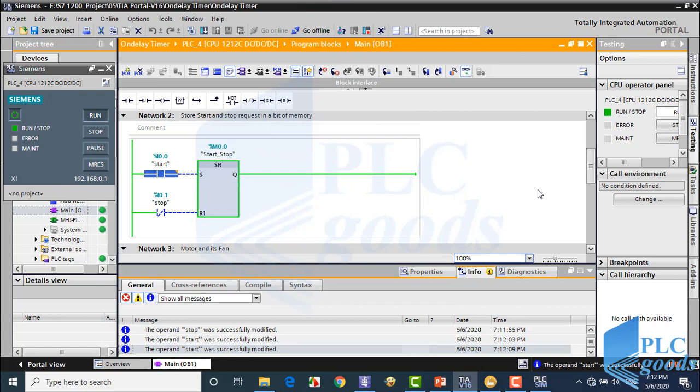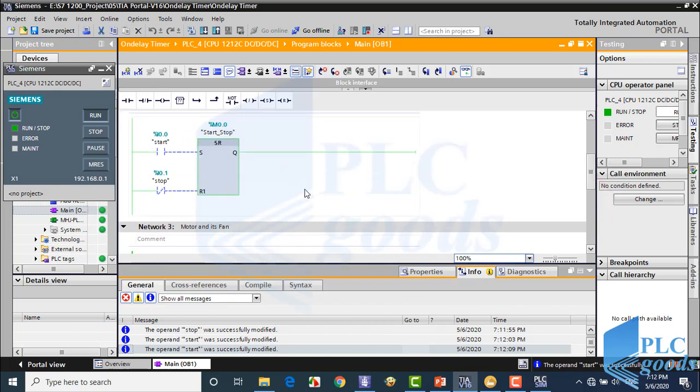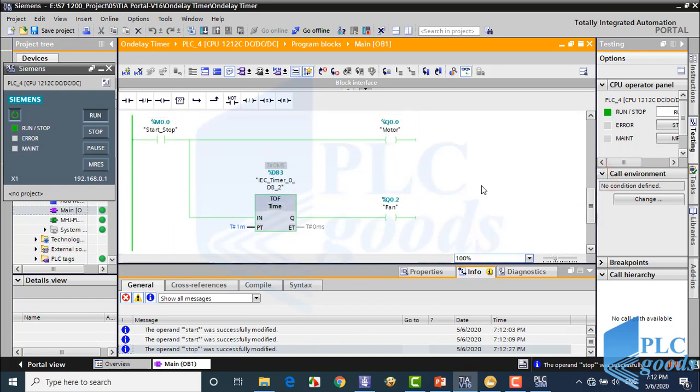Now let me activate the start contact. As you see, both outputs are on. Now if I change the stop contact, it turns the motor off immediately, but the fan is still on. It will be off after 1 minute.